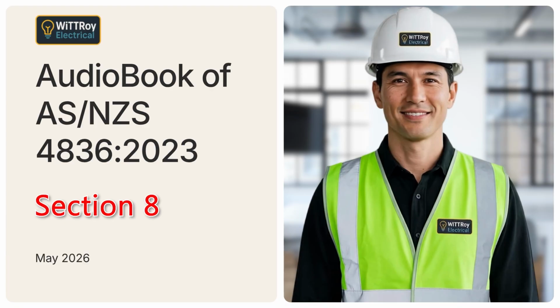When portable RCDs or isolating transformers are used, they should be placed as close as practicable to the point of supply. For example, they should be at the supply end of an extension lead, not at the appliance end. This is important because the extension lead also needs protection where practicable.